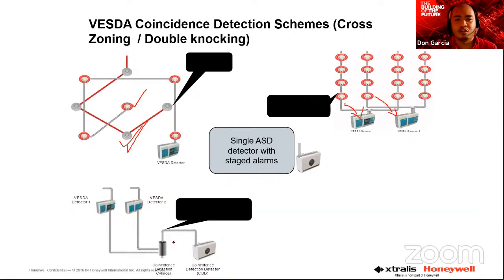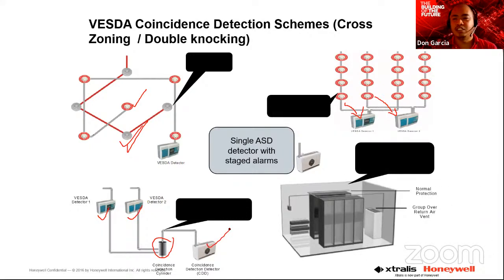So this means we're using a coincidence detection cylinder, where the smoke collected by stage 1 and stage 2 detectors accumulates, and only then does the suppression system activate. Number 4 is just to adjust the sensitivity of the ASD detector going to stage 2, which determines how the sprinkler system or suppression system activates.